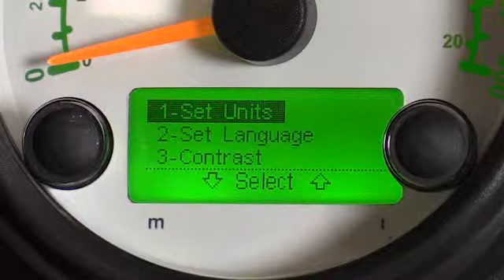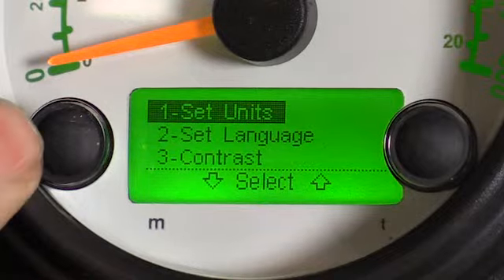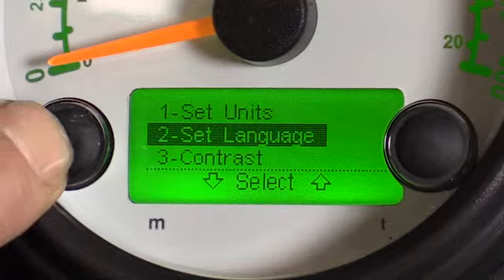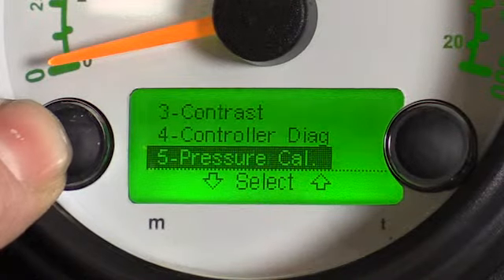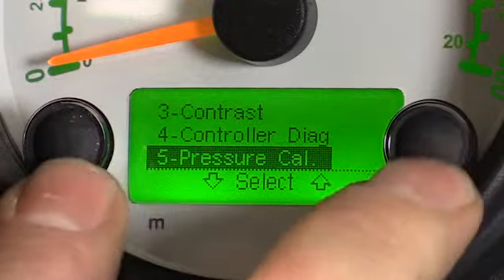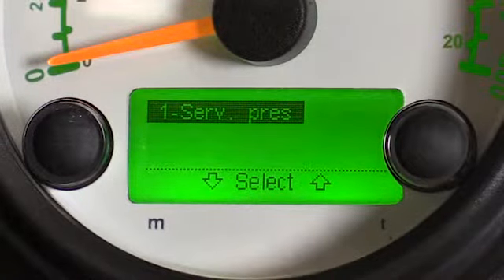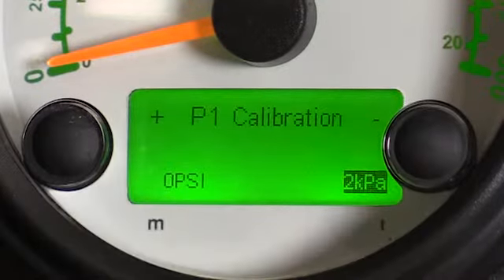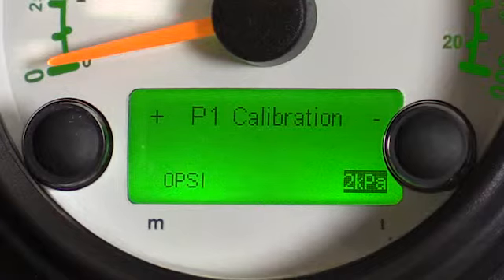Now we would like to demonstrate doing a pressure calibration. This is something that should be done every time the unit comes back from a rent, getting it ready for the next rent. Once pressure calibration is highlighted, press the M and T buttons at the same time to activate this selection. Use the M and T buttons to change the parameter to the desired setting.